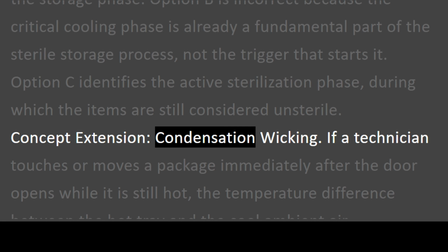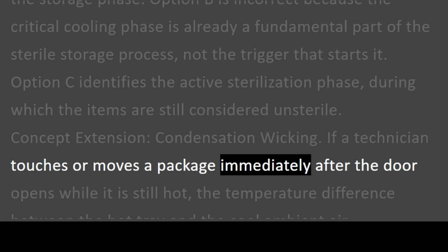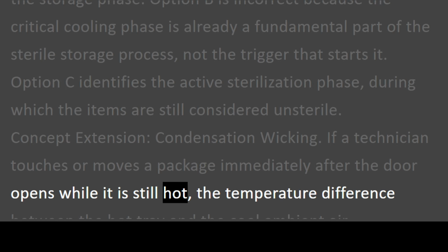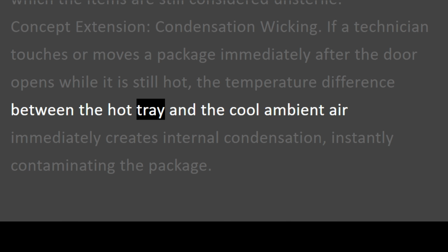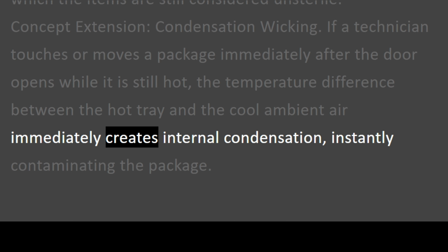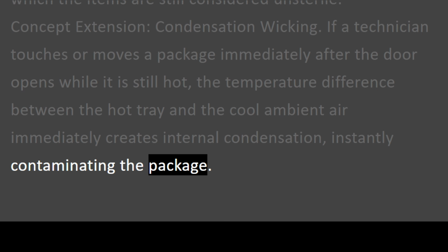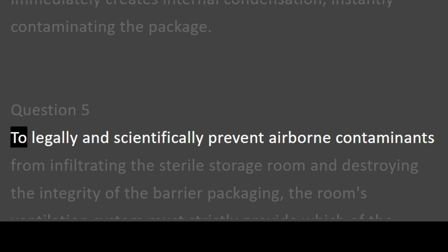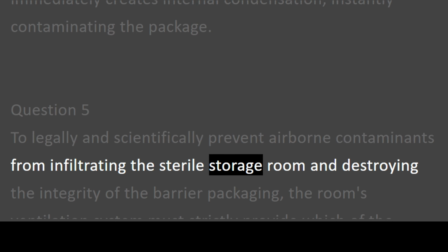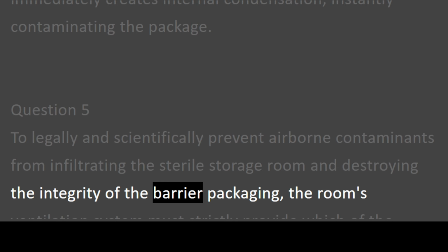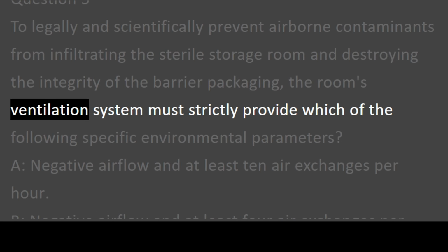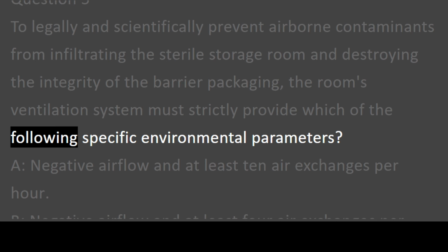Concept extension, condensation wicking. If a technician touches or moves a package immediately after the door opens while it is still hot, the temperature difference between the hot tray and the cool ambient air immediately creates internal condensation, instantly contaminating the package. Question 5. To legally and scientifically prevent airborne contaminants from infiltrating the sterile storage room and destroying the integrity of the barrier packaging, the room's ventilation system must strictly provide which of the following specific environmental parameters?